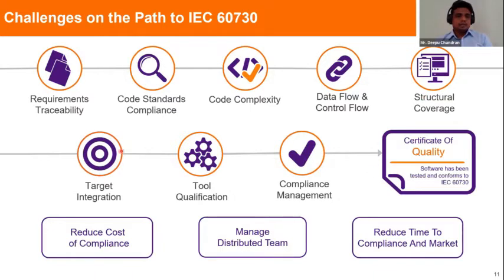All the tests need to be done on the target to ensure that memory and timing related aspects are taken care of, and the tools used need to be qualified. Unless you use a qualified tool, you can't claim credibility for the output generated, because the tool itself can introduce an error into your software or fail to detect an error. So a confidence level needs to be established on the tool, and a certified or qualified tool needs to be used, along with compliance management with respect to process activity according to 60730.